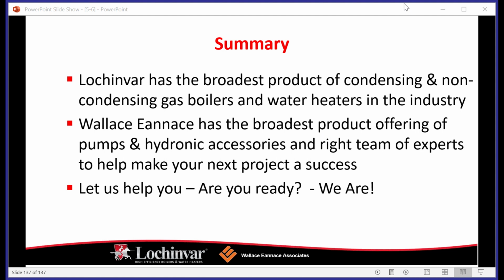So again, owner maintenance, really not much to do. This is very basic rudimentary stuff we're going to go through. And again, if you're retaining your customers like you want to, you're going to do this through. So again, you need to look for leaks. You're going to check and make sure that the relief valve isn't dripping or hasn't popped off. There's no water standing on the floor adjacent to the boiler.